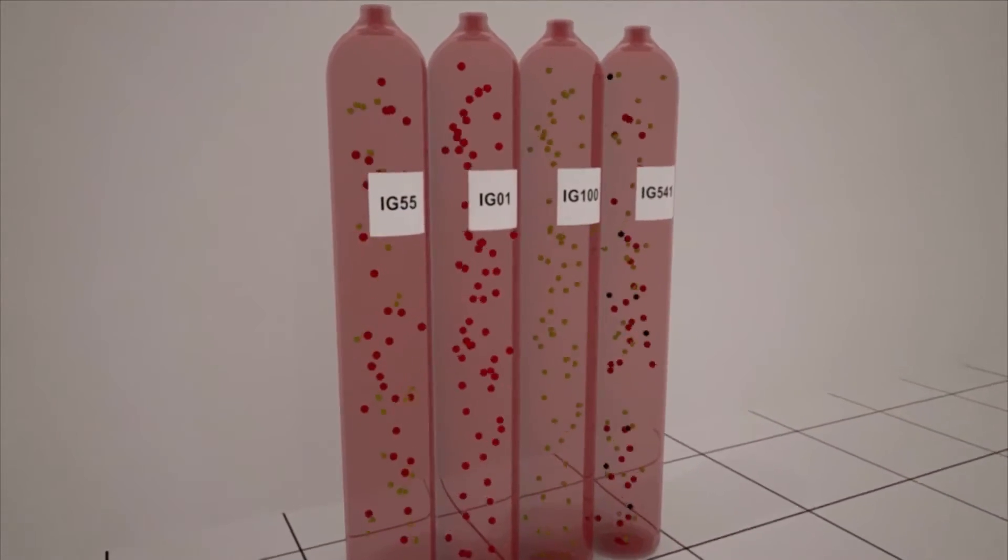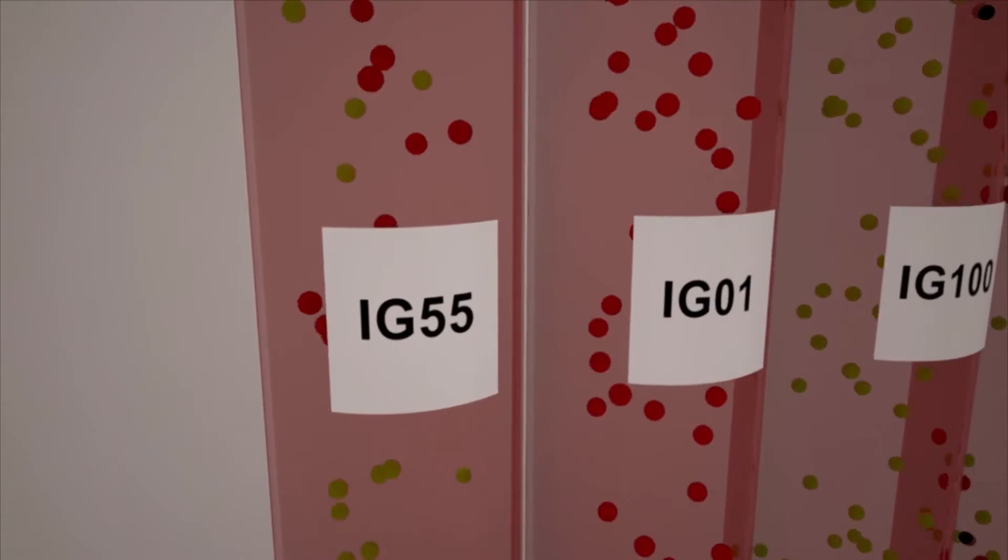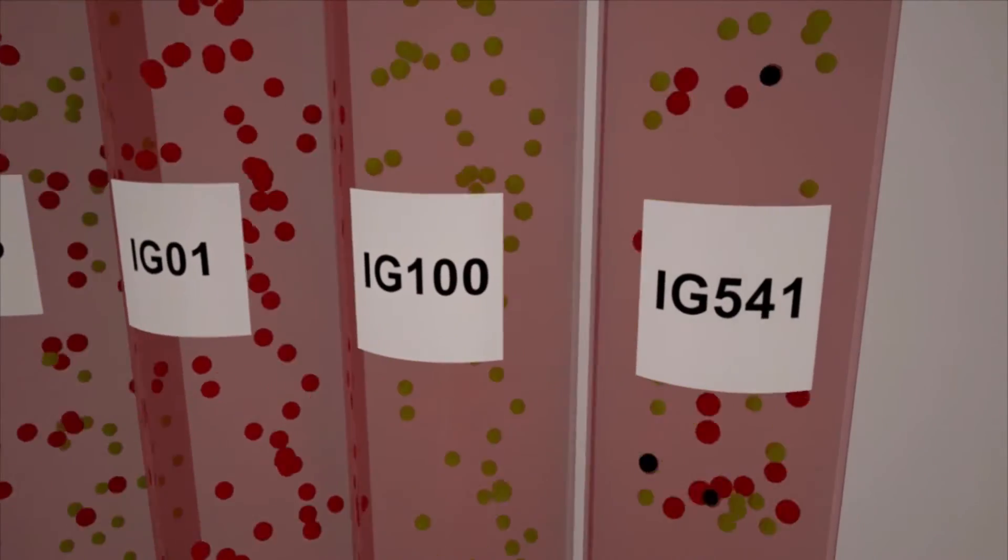A further product improvement made by Fike with ProInert 2 is the choice of inert gases available, as listed in many international standards. You can now choose from IG55, the traditional ProInert gas; IG01, Argon; IG100, Nitrogen; and IG541, also known as Inergen.